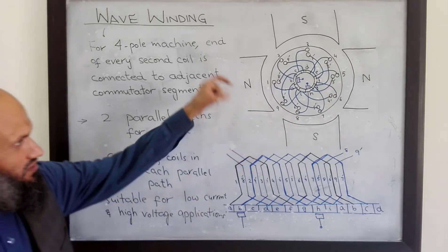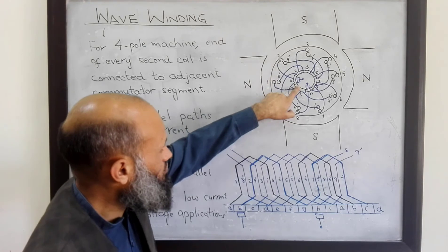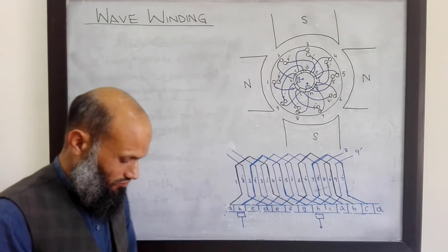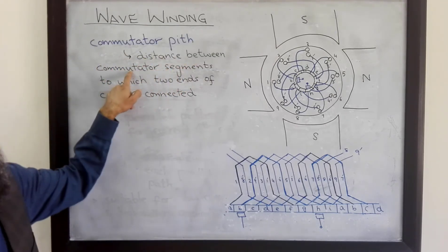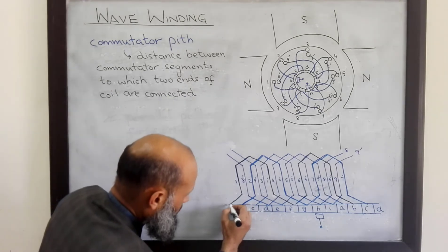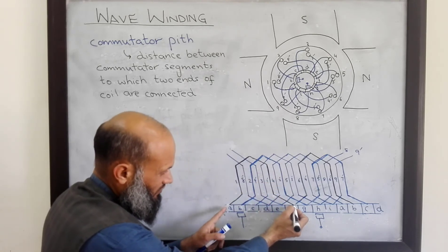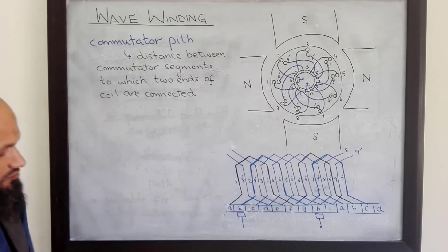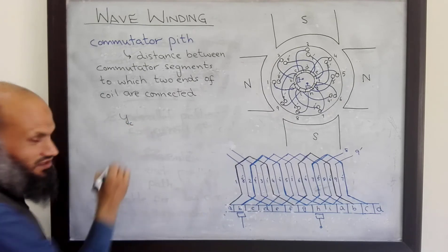We are left with only one question: how did I decide that if coil one is connected to A, then one-dash should be connected to F? To clarify it, we define some terminology. We define commutator pitch. Commutator pitch is the distance between the commutator segments to which the two ends of the coil are connected. For example, for this particular machine, one end of this coil is connected to A and the second end is connected to F. What is the distance between these commutator segments? 1, 2, 3, 4, 5 — so commutator pitch for this machine is 5.